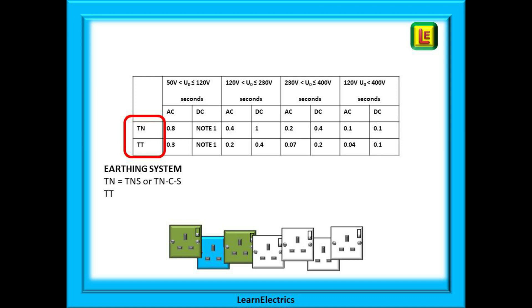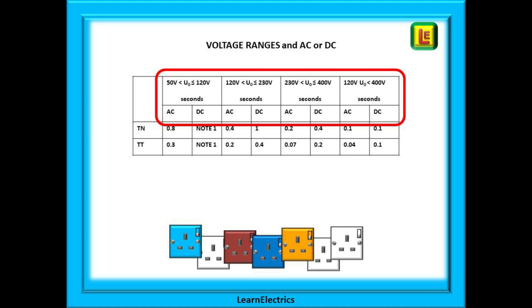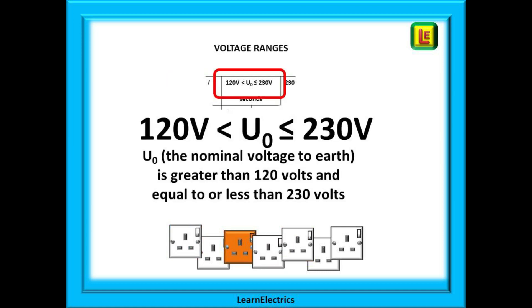First of all let's take a look at the table. On the left, highlighted in red, we have a choice of earthing system — either TN for TNS or TNCS, and TT for those systems using earth rods or similar. At the top of the table we have four voltage ranges to choose from — it is important to choose the correct range. Within each range we have a further choice of AC voltages or DC voltages. U0 is the nominal voltage to earth; in a domestic property U0 is the nominal voltage between line and earth, which we call 230 volts.